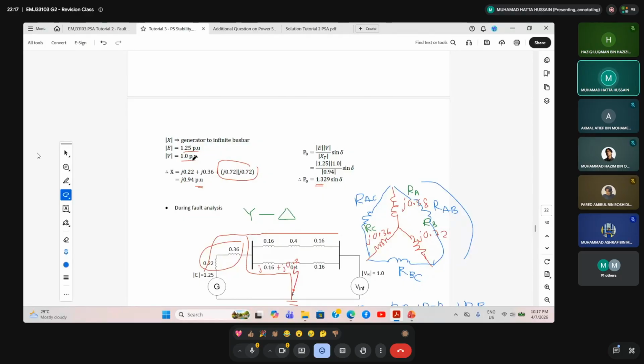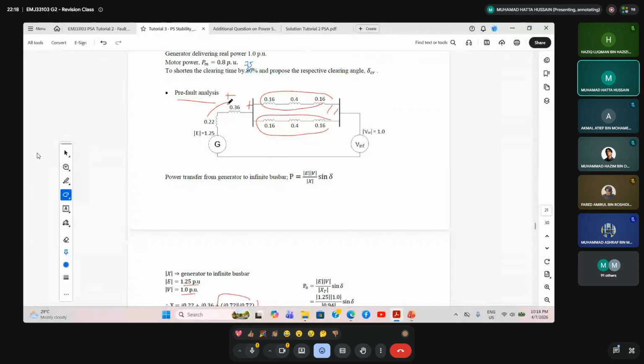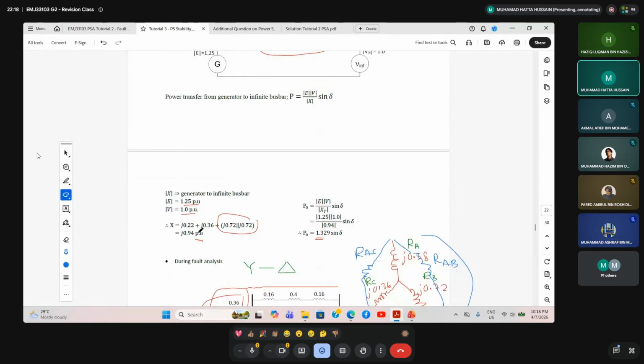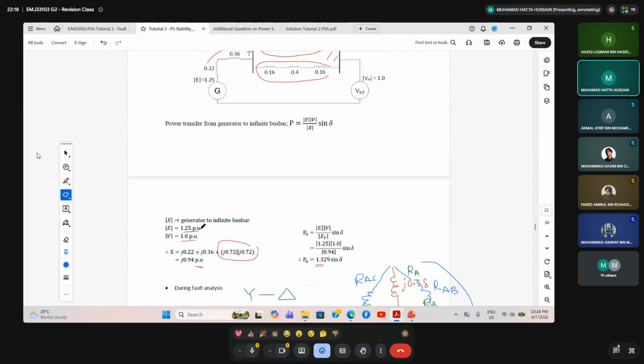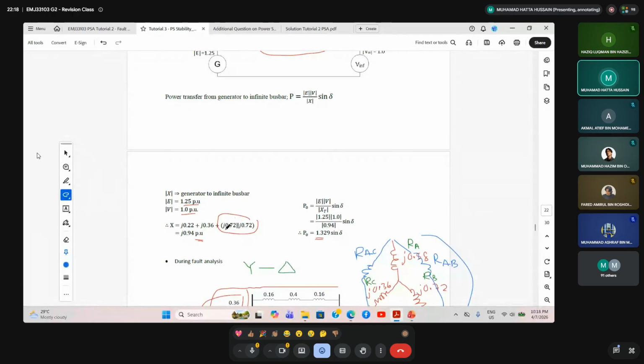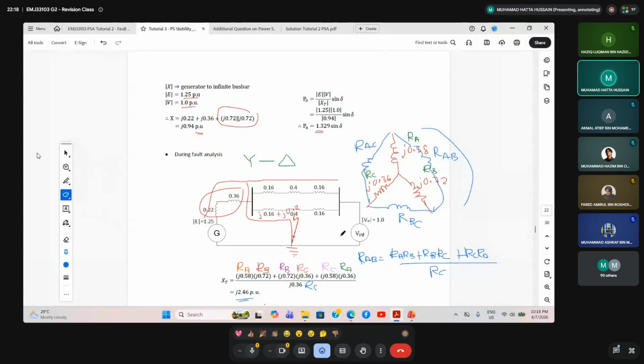Okay, and again, we have to find the transfer reactance or the total reactance, X here. From X here, we know that this is in series: 0.22 plus 0.36, and then plus this one in parallel with this one. So we have j0.22 plus j0.36 plus j0.72 parallel with j0.72, so we have j0.94 per unit. And again, we substitute the X value into the power angle equation, so we have 1.329 sine rotor angle. Okay, remember one thing.